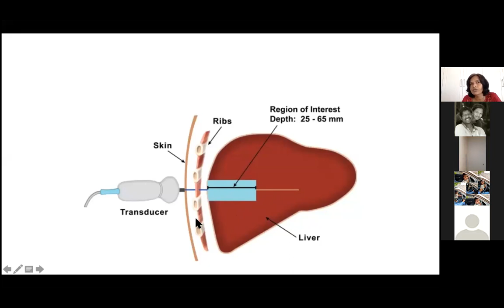Not only the stiffness, it also to a certain extent gives the fat content in the liver. As I told you, F0, F1, F2, F3, F4, and F4 is cirrhosis. When you look at the values in a transient elastography or any liver stiffness measurement like the FibroTouch or FibroScan, values are normally from 2.5 to 75. Any value less than 7, you can see that it is green, means there is very mild or no fibrosis. Whereas any value above 12.5 or 13 or 14 means it is F4 or cirrhosis.